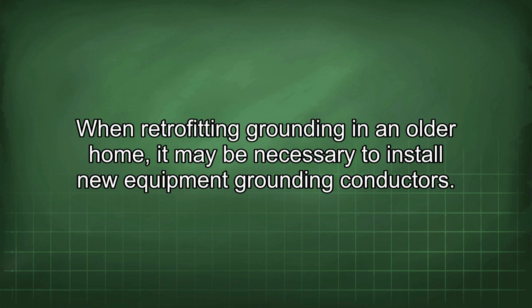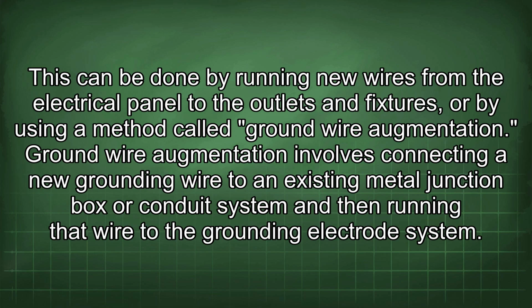When retrofitting grounding in an older home, it may be necessary to install new equipment grounding conductors. This can be done by running new wires from the electrical panel to the outlets and fixtures, or by using a method called ground wire augmentation.